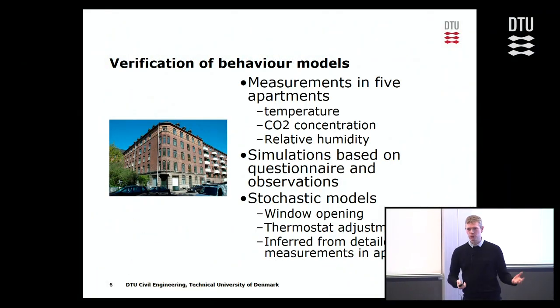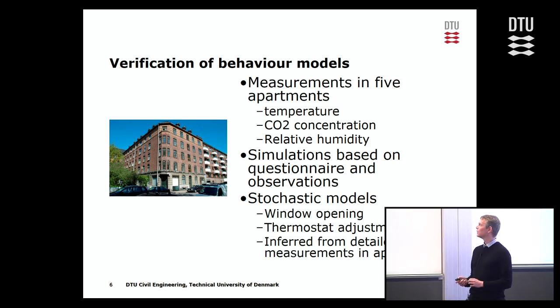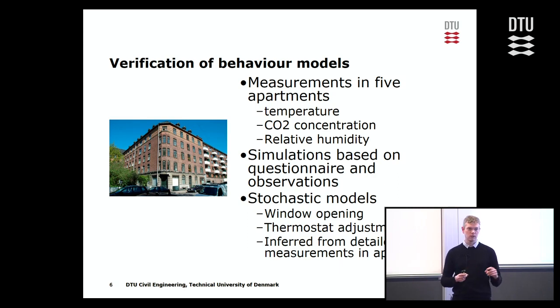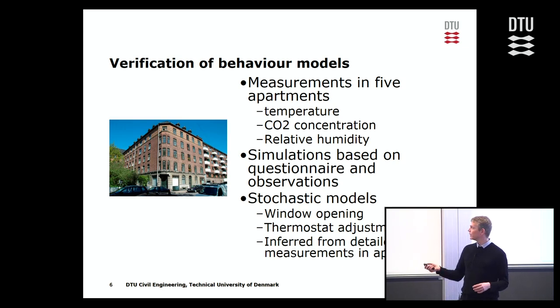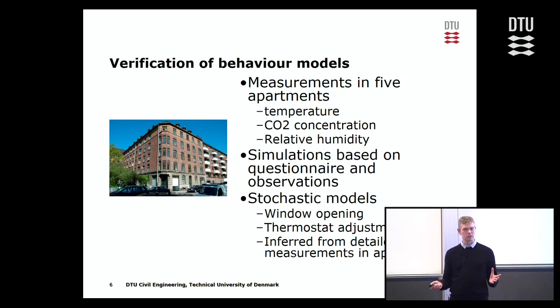We wanted to see how well these models perform - are we actually capable of making realistic predictions, or is it completely wrong? So we went into five apartments and made very detailed measurements of temperature, CO2 concentration, and relative humidity. We had questionnaire surveys, we interviewed the occupants about their electricity consumption and when they were home. We made observation studies to capture all the boundary conditions of this building, then simulated it including these models in the simulation program.